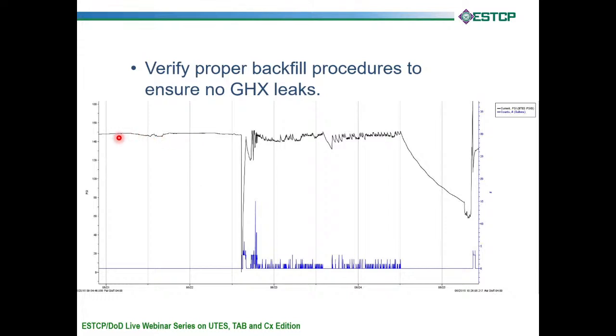Sitting here in Macon, Georgia, we monitored this project, which was in Albany, Georgia, and we could see our pressure was holding steady, and it would drop sometimes when the pipe expanded. And when the pipe contracted, the pressure would go up. But our pump is off, so we're not worried. Then all of a sudden, one day, the pressure bottoms out, and the pump starts cycling. And it cycles and it cycles.